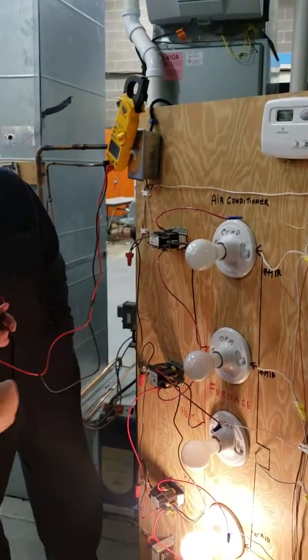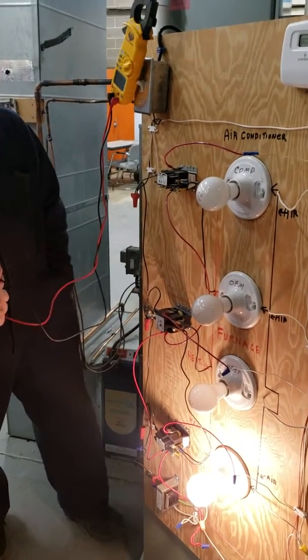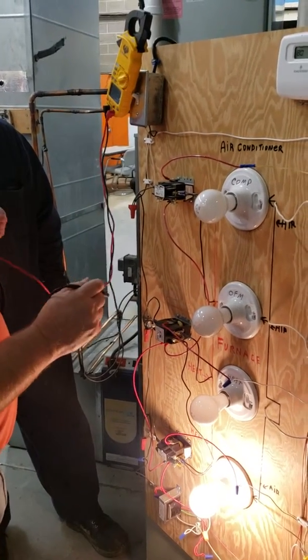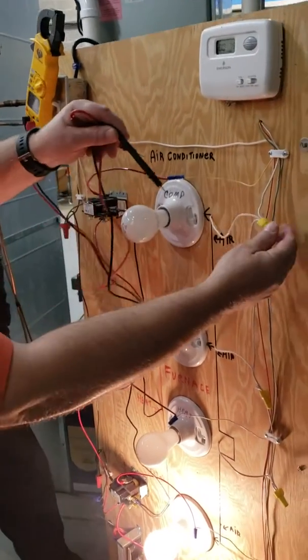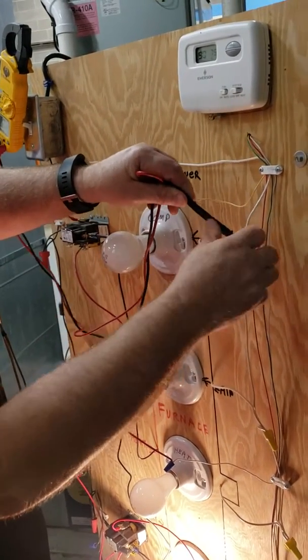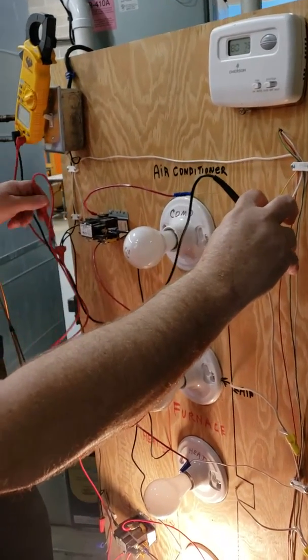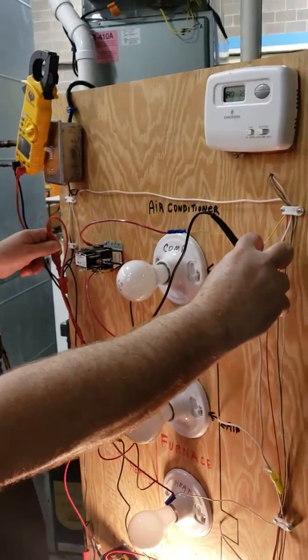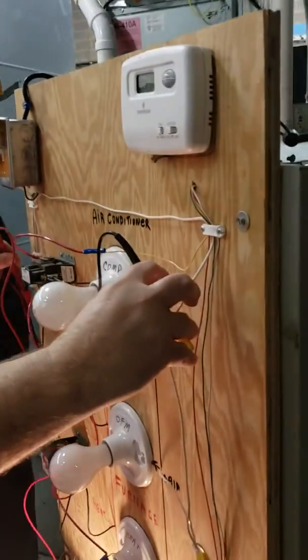Call for, so my outdoor fan motor, my compressor, and my indoor fan should be running, and it isn't. So first thing I'm gonna check is what? Source. So let's see if we have a source. Do I have a source? Yep, I sure do. Okay.